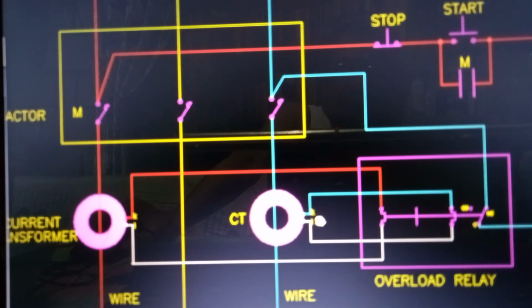The purpose of the current transformer is to reduce the current flowing to the overload relay. Just like on the kilowatt-hour meters with current transformer, the purpose is to reduce the current because the current capacity of the kilowatt-hour meter is small. So similarly, in this case, we can use a small current rating of the overload relay because we are using the current transformer.